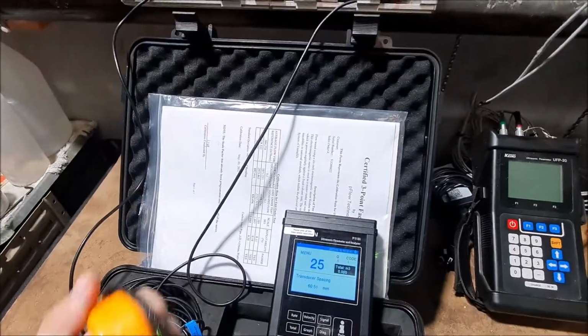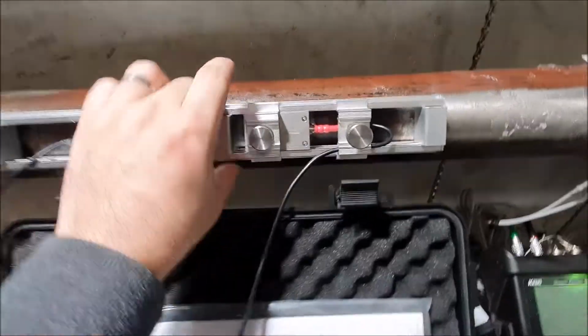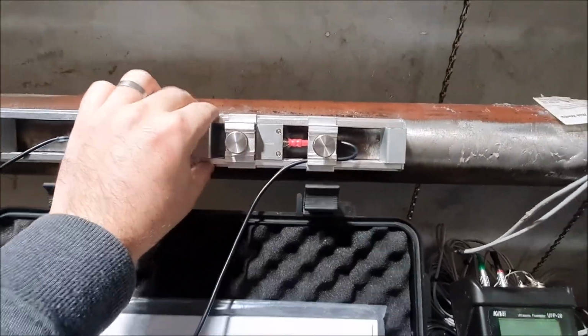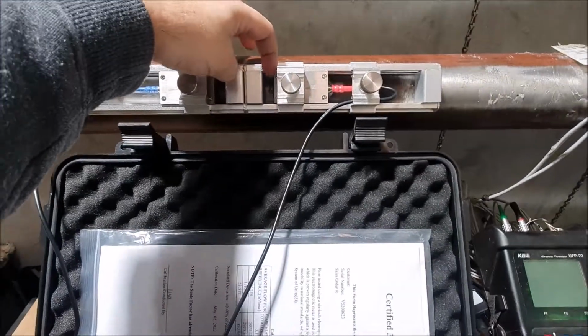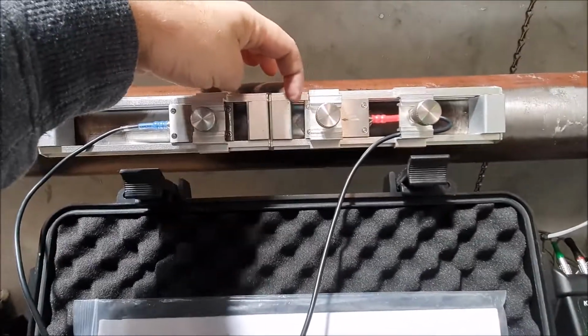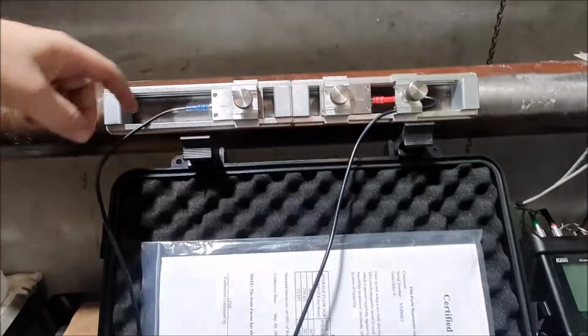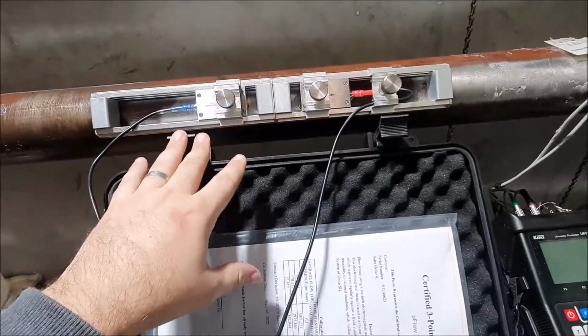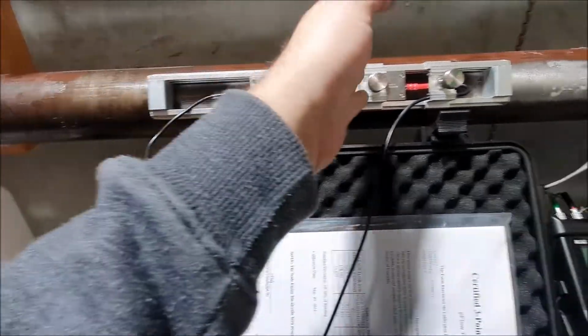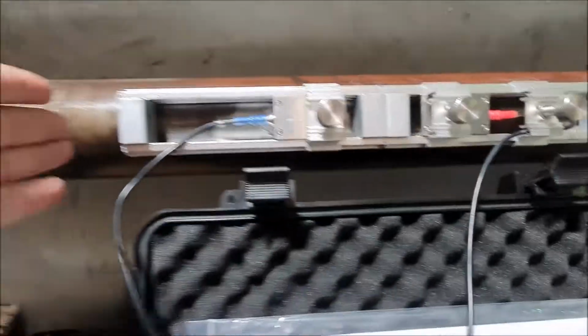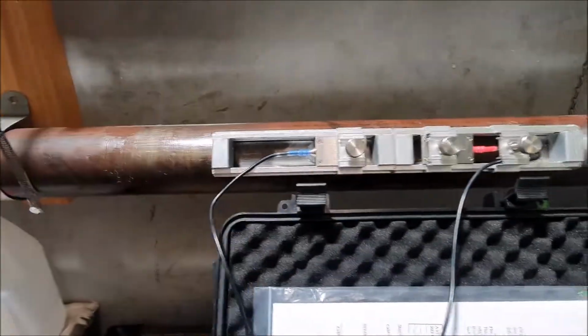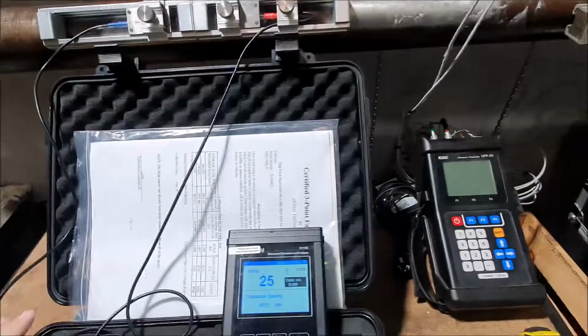So that's where your tape measure will come in. You just mount your one transducer frame, then manually measure the distance with your tape measure from the front face of your transducer. Say you had a big pipe and you needed to space them at 200 mil apart. Then you just mount your frame, separated, and manually measure your distance with your tape measure just to get that correct spacing.